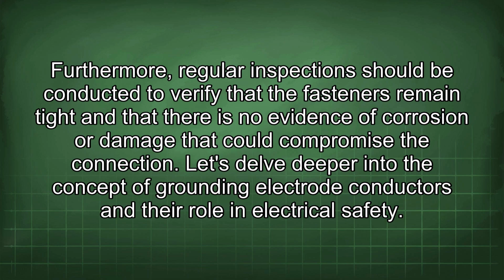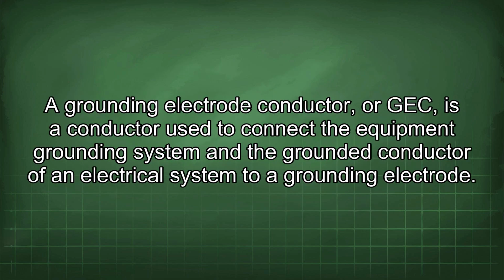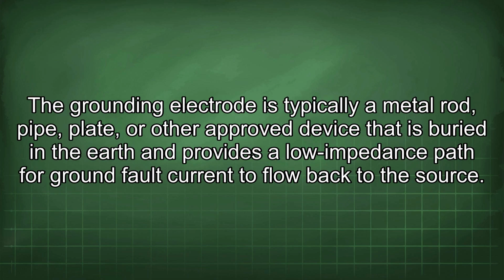Let's delve deeper into the concept of grounding electrode conductors and their role in electrical safety. A grounding electrode conductor, or GEC, is a conductor used to connect the equipment grounding system and the grounded conductor of an electrical system to a grounding electrode. The grounding electrode is typically a metal rod, pipe, plate, or other approved device that is buried in the earth and provides a low impedance path for ground fault current to flow back to the source.